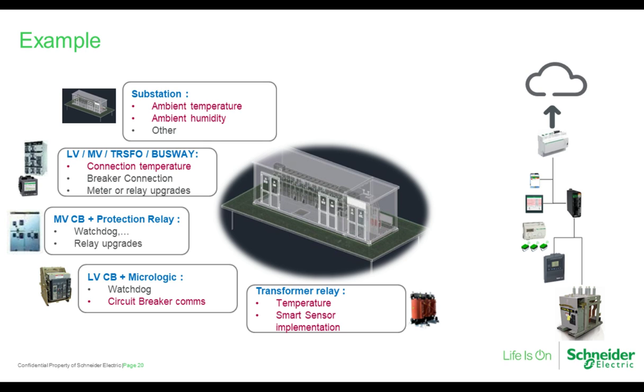So we can upgrade the low voltage, we can upgrade the medium voltage, we can add, again, temperature sensors to all of these devices so that we can monitor the heat that's occurring and look for failures. We can also look at transformers. We can upgrade the transformer relay. There's a lot of new relays out there. We can look at the temperature. We can add that into the software, the temperature sensing within the transformers that might already be there.